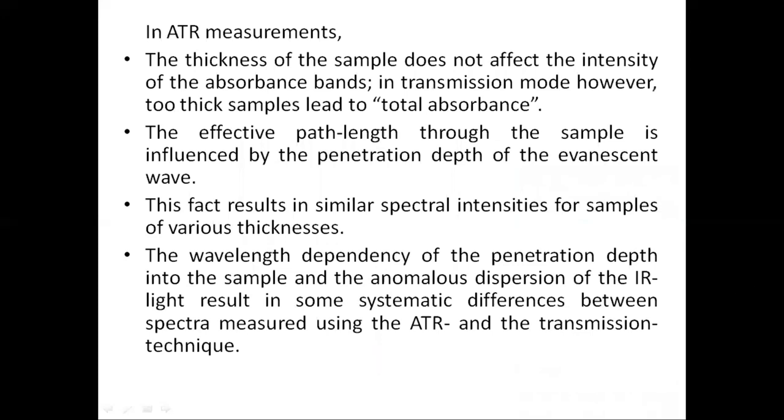In ATR measurements, the thickness of the sample does not affect the intensity of the absorbance bands. In transmission mode, however, too thick samples lead to total absorbance. So in transmission mode, sometimes total absorbance will take place due to too thick a sample layer, but in ATR that is not the case. The thickness of the sample does not affect the intensity of the absorbance band. The effective path length through the sample is influenced by the penetration depth of the evanescent wave. This fact results in similar spectral intensities for samples of various thicknesses.